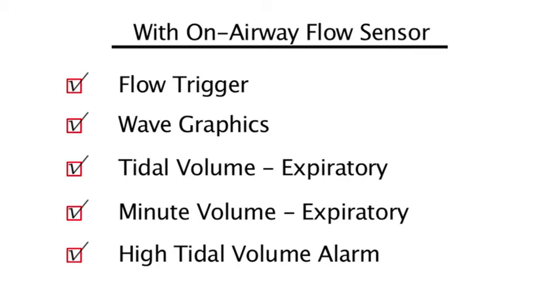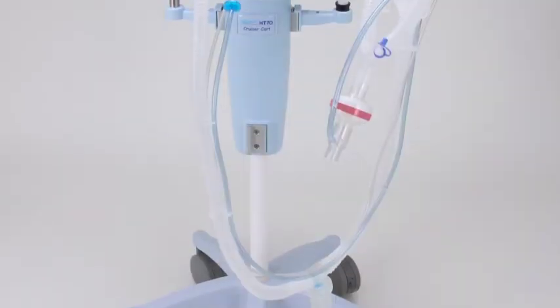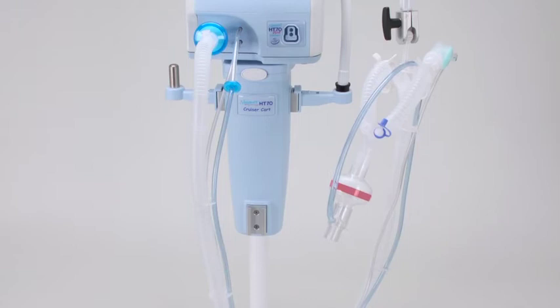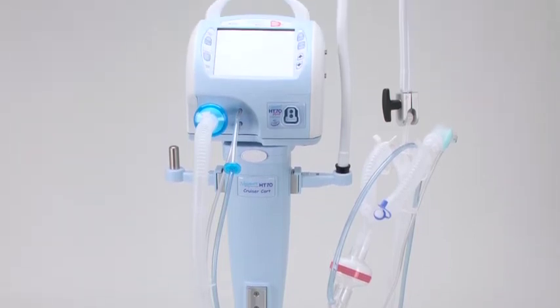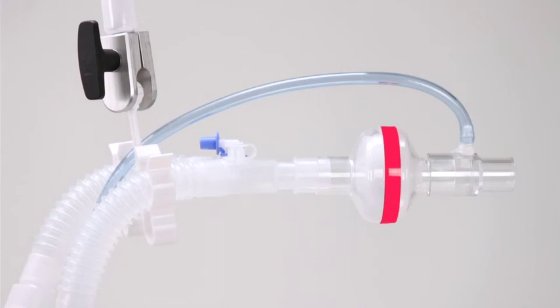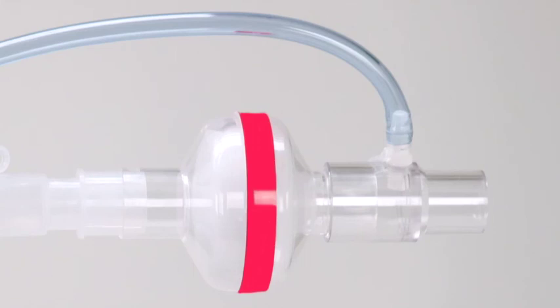The next choice you will need to make is whether you will provide the patient with passive humidity using an HME or active humidity using a heated humidifier. When using an HME without the on-airway flow sensor, you will attach the HME directly to the Y connector. For the best circuit disconnect detection by the low pressure alarm, it is recommended that you connect the proximal pressure line to a connector on the patient side of the HME, rather than to a port on the circuit Y. To do this, you will need to add an extra T-piece like this one to the patient side of the HME, disconnect the proximal pressure line from the Y connector, cap that port with the blue cap, then connect the proximal pressure line to the T-piece.